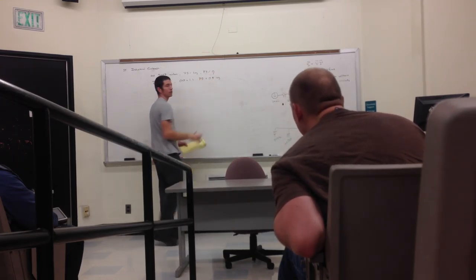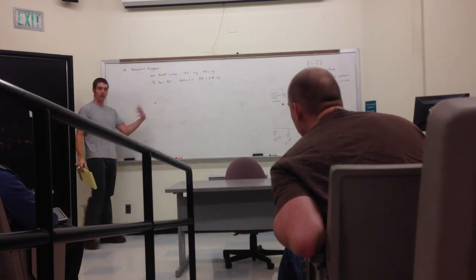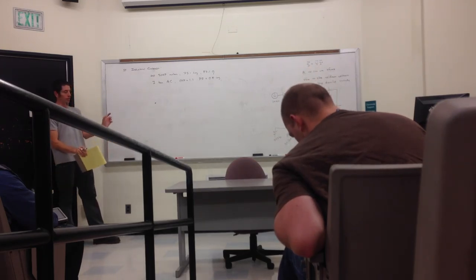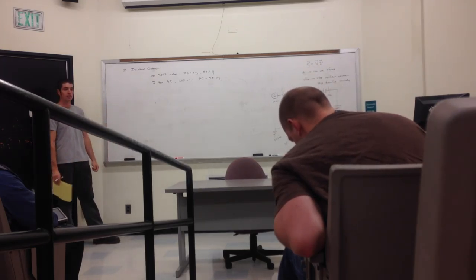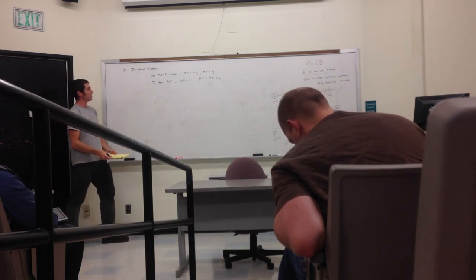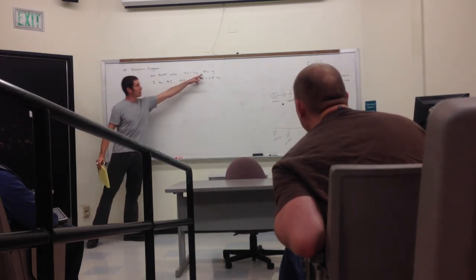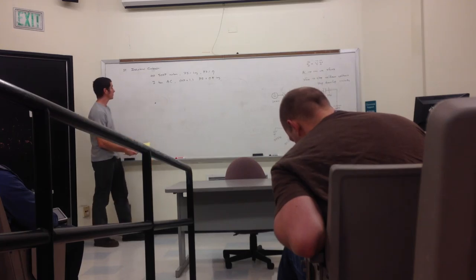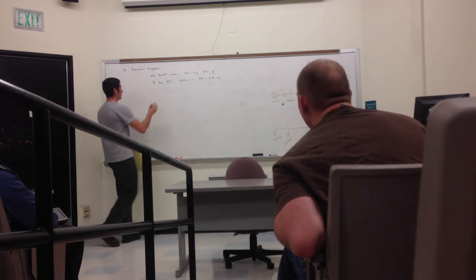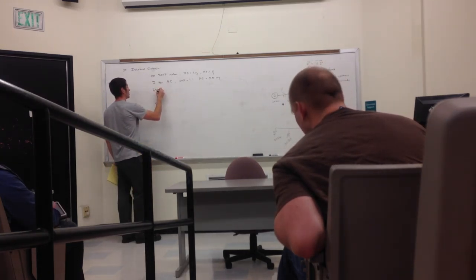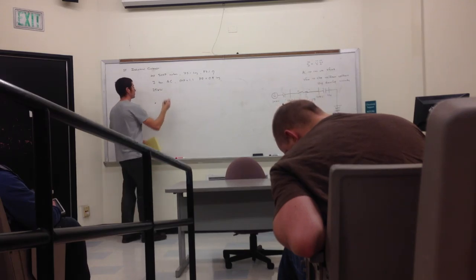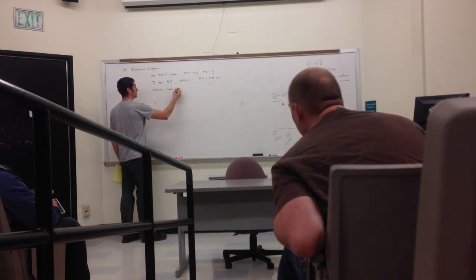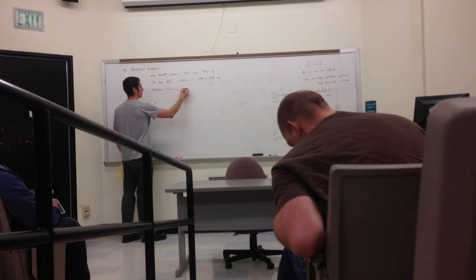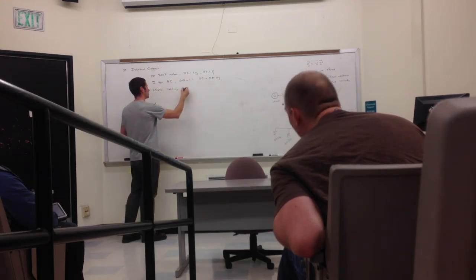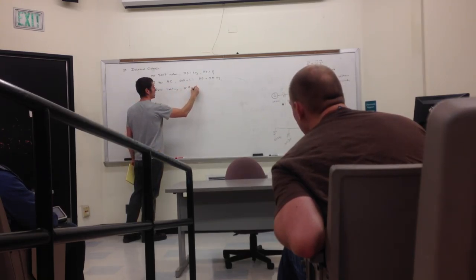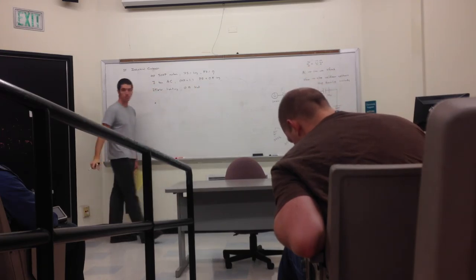So this is all information gleaned from what's called the nameplate. You walk up to the machine with the little tag and pull this information off. 87% efficiency, yeah. All right, they've got 25 kW in lighting, this is about right, and these appear to be new electronically ballasted systems, so they have a leading power factor too.